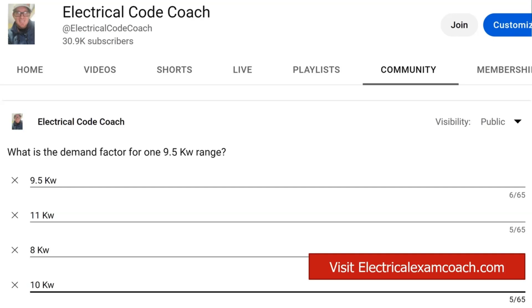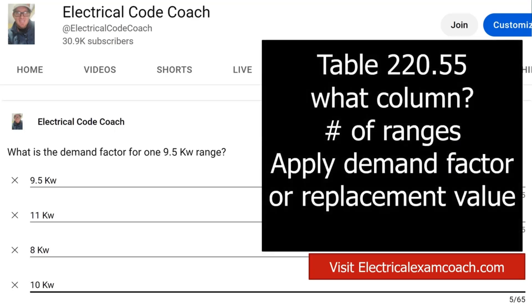This answer is going to be found in Table 220.55. So we're in Article 220, looking specifically at Table 220.55. The first thing we ask ourselves is what column does our range fall in — columns A, B, or C. In this case, it's going to fall into Column C: ranges that are not over 12 kW but are greater than 8.75 kW.